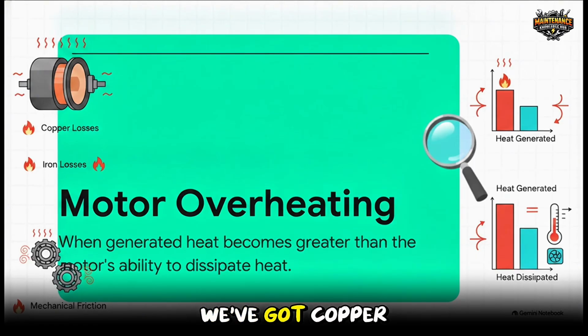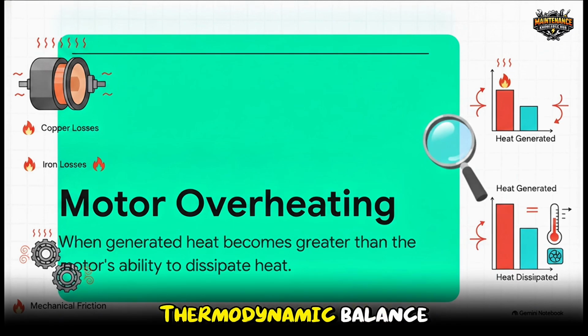You know the drill. We've got copper losses in the windings, iron losses in the core, and mechanical friction in the bearings. If the heat being generated outpaces the heat being dissipated, well, you get a dangerous fever. It really just comes down to a fundamental thermodynamic balance.